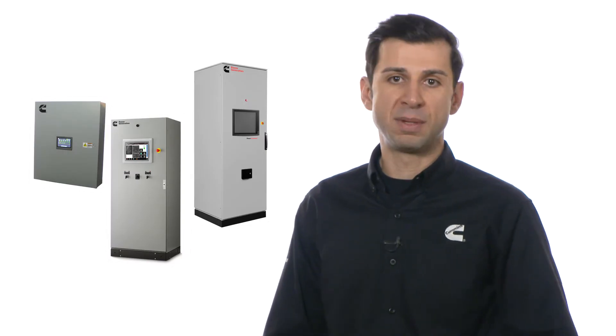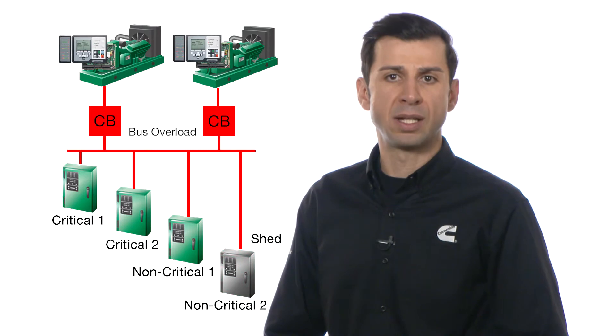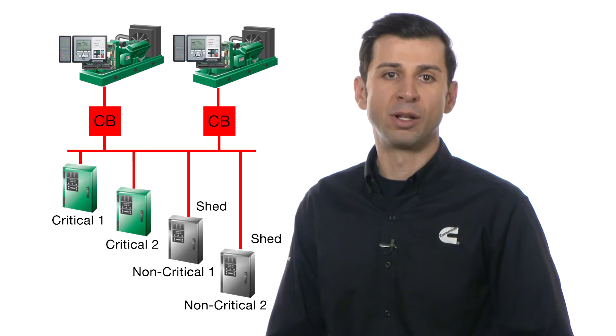The transfer switch can receive a load shed command from a generator or a system-level control such as a DMC. When the command is received, the ATS transfers the connected load from the generator to the center-off position to prevent the generator from becoming overloaded.